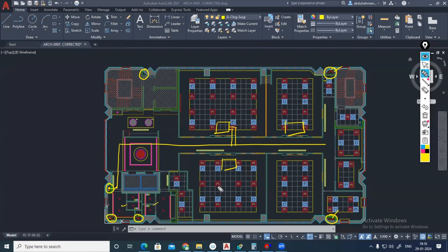Why are we not taking it through this area? If it is possible, we can take the chilled water pipe through training room one or training room two or whatever. But the problem is, if you want to do some maintenance, you have to evacuate this area, right? Since the pipe is going above the false ceiling, you have to evacuate the area, and only then can you do the maintenance, so the function will be affected.